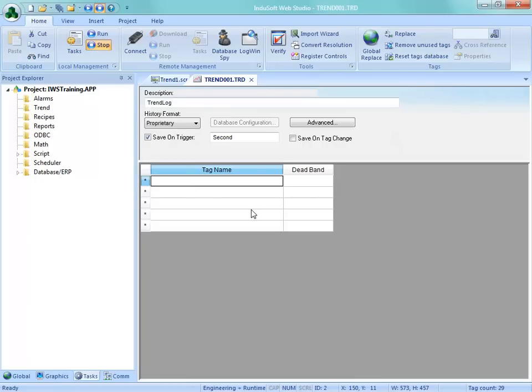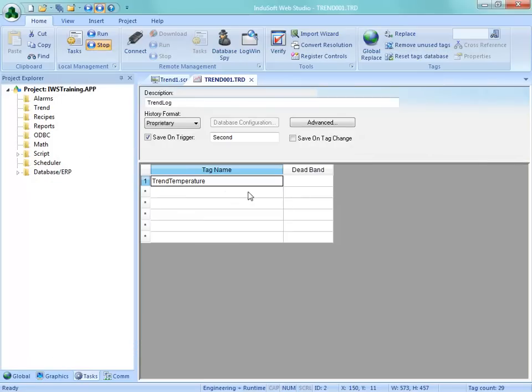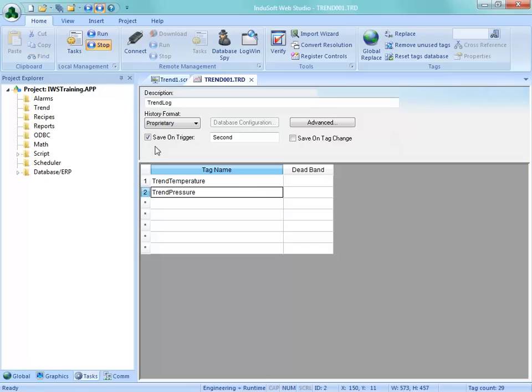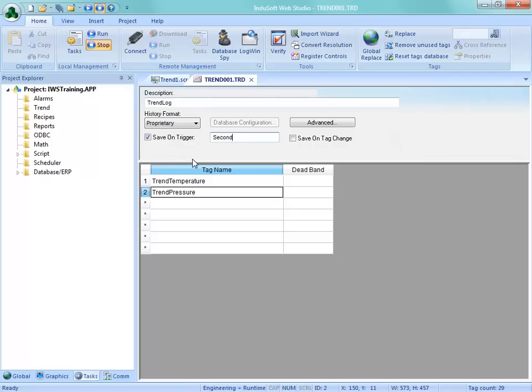We're going to log any tags in here - I'll add trend temperature and trend pressure. We're going to log these based on the save on trigger checkbox, using the seconds clock from the computer where the runtime is running. This value counts from 0 to 59 like the seconds clock, and every time that changes it will trigger and log these values to the file. It stores that data in the HST folder in your project.